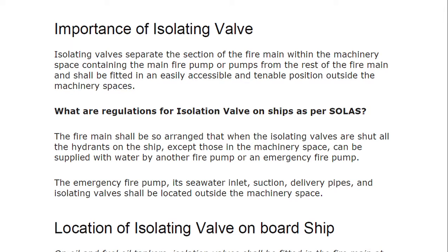The fire pump is generally located in the machinery space — the GS pump is generally located in the bottom platform of the engine room. The surveyor will ask you the location. The isolating valve shall be fitted in an easily accessible and tenable position outside the machinery space — it must be outside the machinery space.